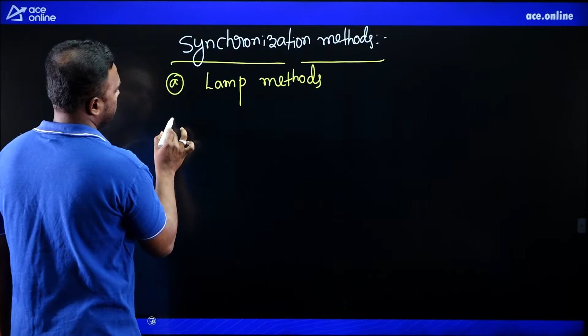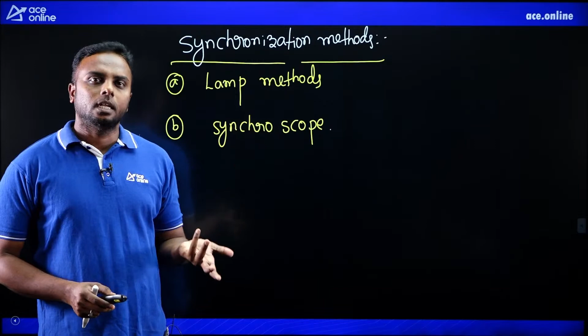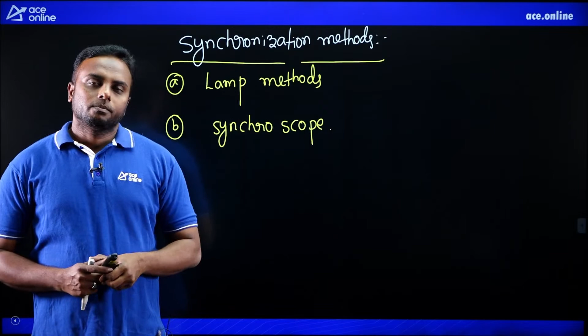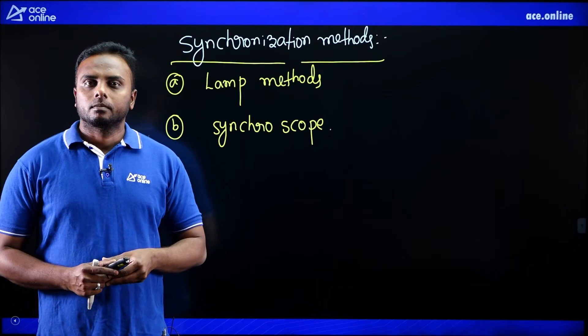In synchronization we mainly have two methods. The first one is the lamp method, and the other is the synchroscope. The synchroscope is an instrument we use to compare the frequency of the two systems directly, and here the phase sequence will not come directly. Anyhow, we will see only the lamp methods. With the synchroscope, by using an instrument we directly compare the frequency of the two systems, bus bar and alternator, so frequency comes easily in this method. But the lamp methods are important. Using lamp methods we get both phase sequence and frequency at a time.